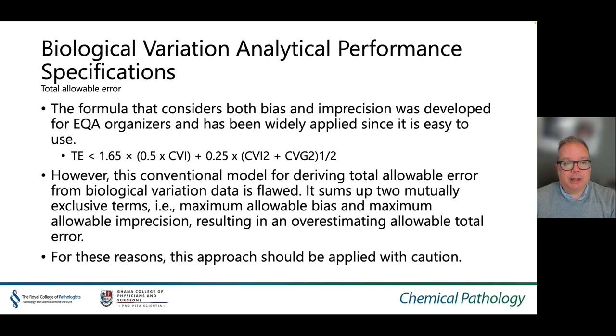Biological variation can also be used to set a total allowable error budget. This formula considers both bias and imprecision and was developed for EQA organisers and is easy to use. However, this conventional model for deriving total allowable error from biological variation is flawed as it sums up two mutually exclusive terms — maximum allowable bias and maximum allowable imprecision — resulting in an overestimation of allowable total error. For these reasons, this approach should be applied with caution.